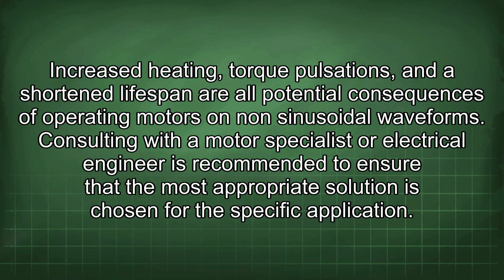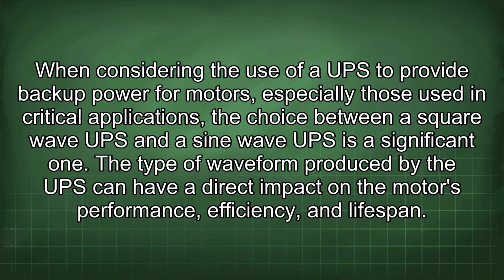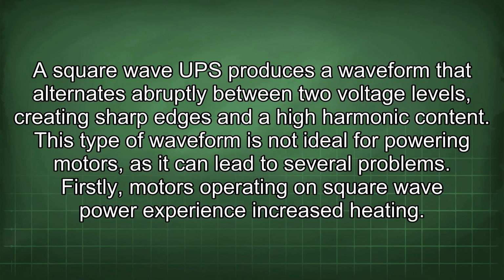When considering the use of a UPS to provide backup power for motors, especially those used in critical applications, the choice between a square wave UPS and a sine wave UPS is a significant one. The type of waveform produced by the UPS can have a direct impact on the motor's performance, efficiency, and lifespan. A square wave UPS produces a waveform that alternates abruptly between two voltage levels, creating sharp edges and a high harmonic content. This type of waveform is not ideal for powering motors, as it can lead to several problems.